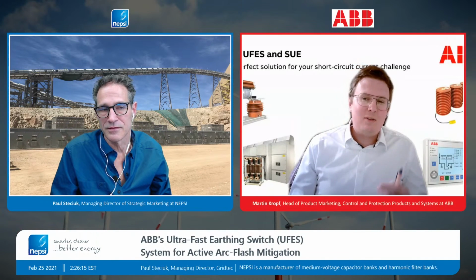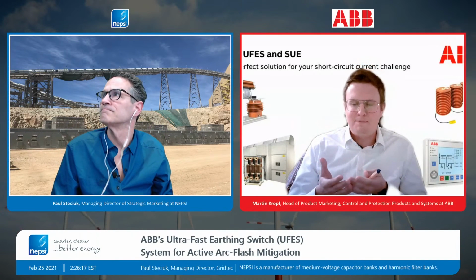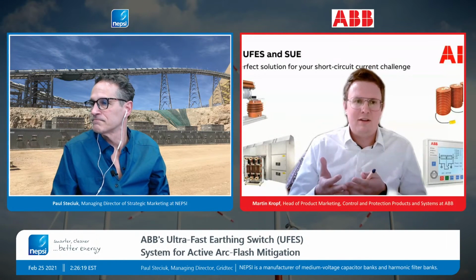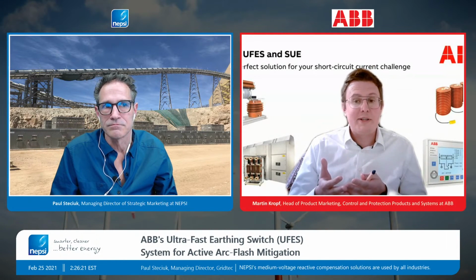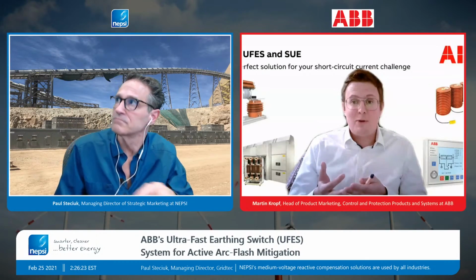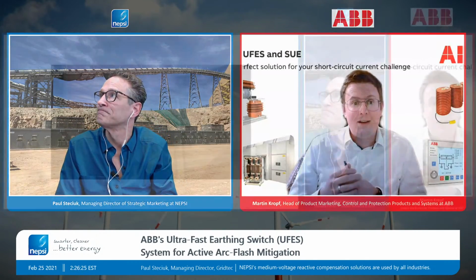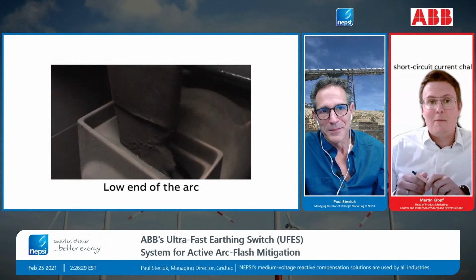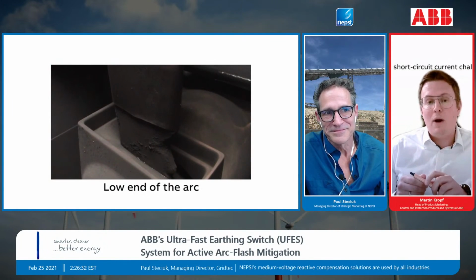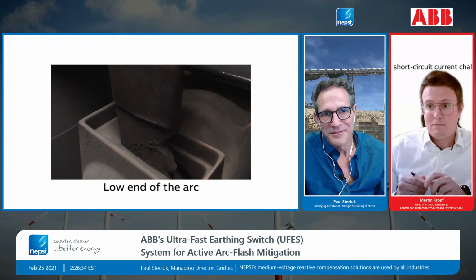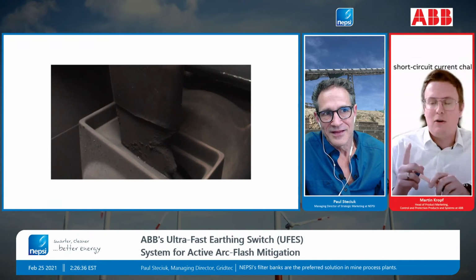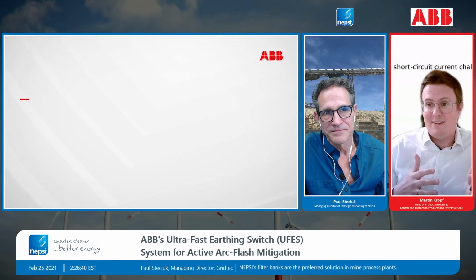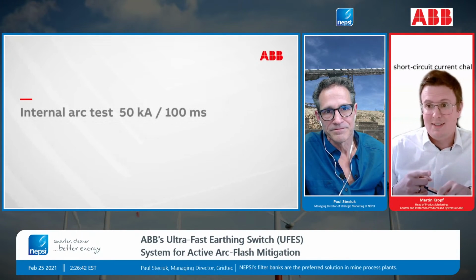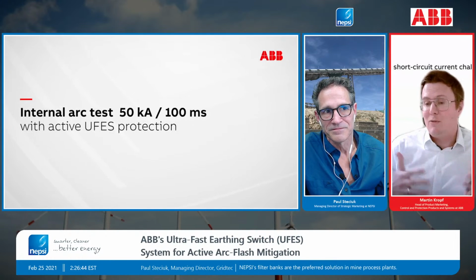What I just said, we had the 100 milliseconds, which means it's a tenth of a normal switchgear rating. The switchgear rating for Unigear is actually 1 second. But now we are back here. You see here the damage in the 100 millisecond panel. So again, a tenth of the duration the switchgear can handle. The switchgear can handle 1 second. So imagine how it looks if 1 second is done.